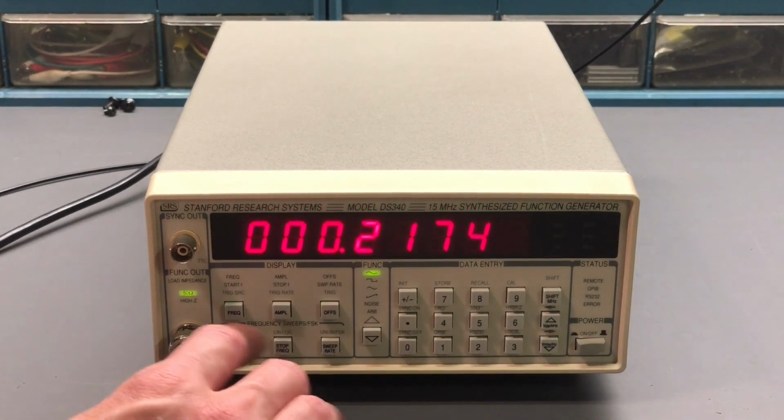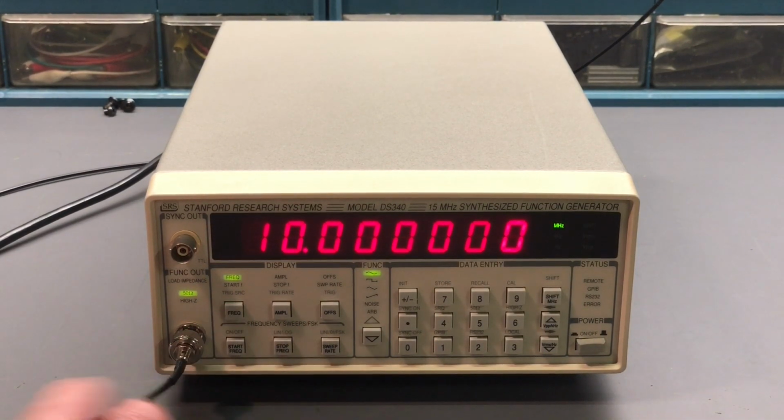And when you're completely done with making these adjustments, you can just press frequency. That takes you out of the calibration setting, and the numbers that you've entered are remembered and are now stored in the RAM chip. So when the instrument starts up, the values in RAM are preserved by that memory backup battery, and it will continue on with all of the calibration settings intact. So really is just that simple.